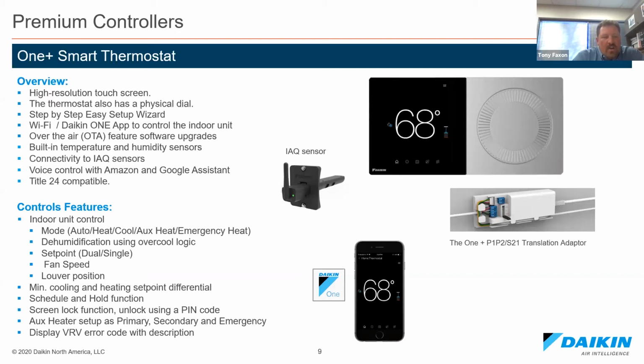Which opens up for further options, say UV or specialized filtration, humidification, or auxiliary fresh air systems. The One+ works with Amazon and Google Assistant if the tenant wants to use voice control. This control option allows for auxiliary heat, and it can be set up for auxiliary primary heat, auxiliary secondary heat, or even emergency backup heat. This is a scheduling thermostat that can control all the normal modes, as well as having an overcool logic for dehumidification. You've got single and dual set points, fan and louver control, error code display with description, and adjustable set point differentials.